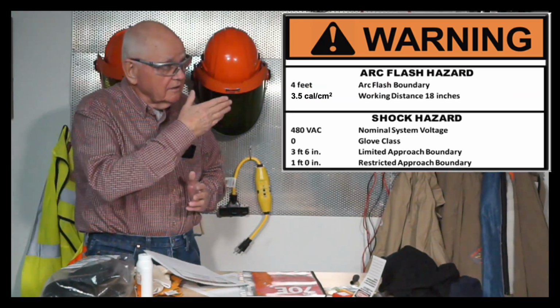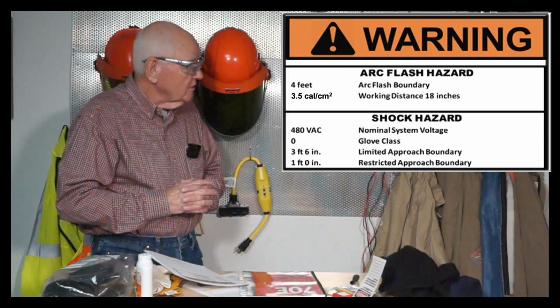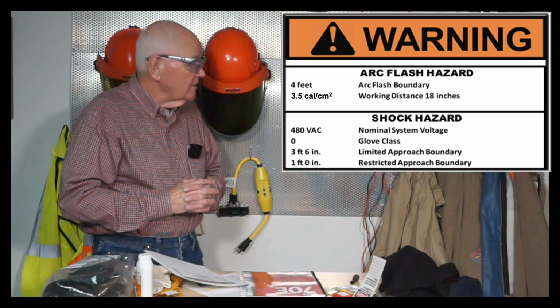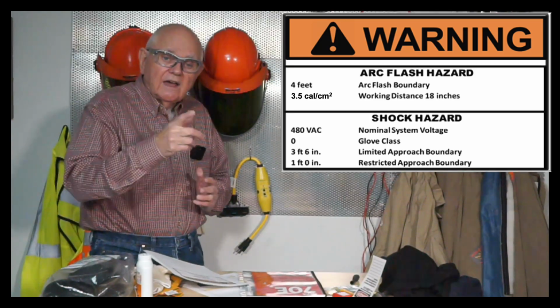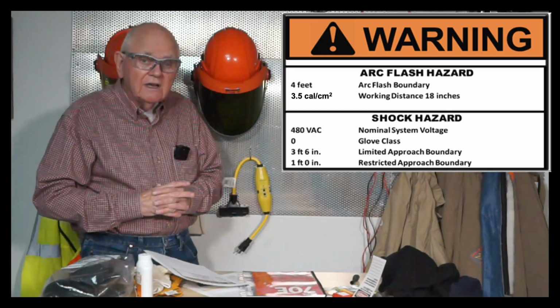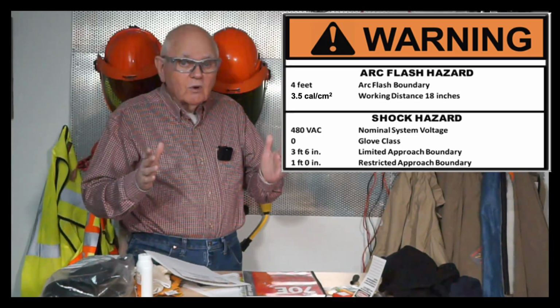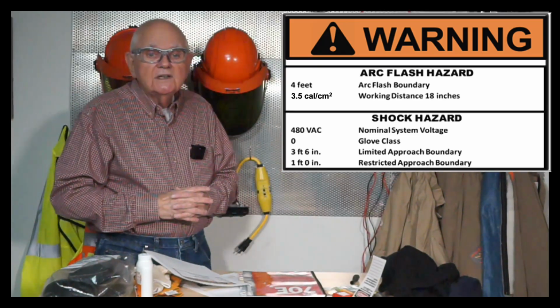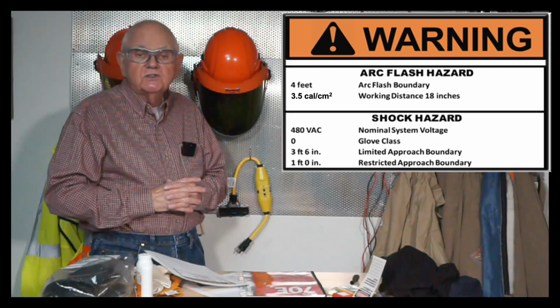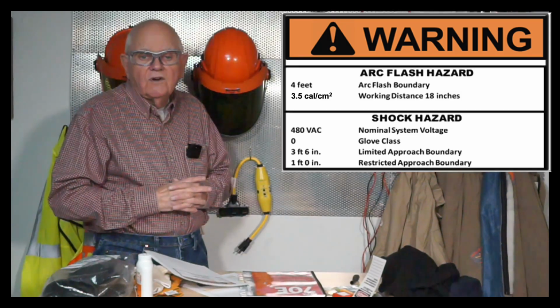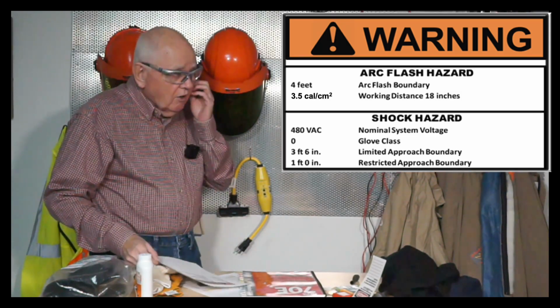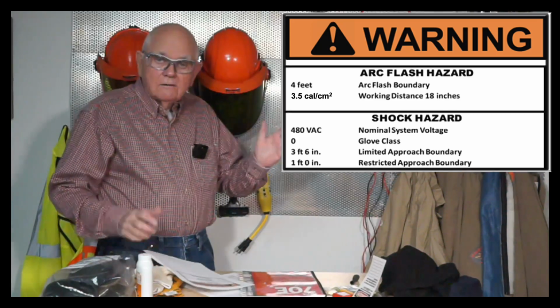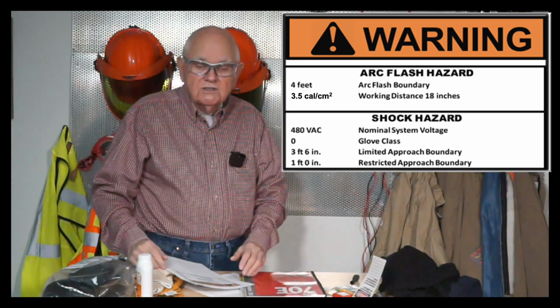So let's take a look at a typical arc flash warning label. This particular label has the minimum requirements on it that are required by the NFPA 70E standard. That's found in section 130.5(H) in your electrical safety work program. Wherever you address your incident energy analysis and so on and so forth, that's where you should be finding this information. So up at the top it says warning. Right, warning, arc flash hazard.